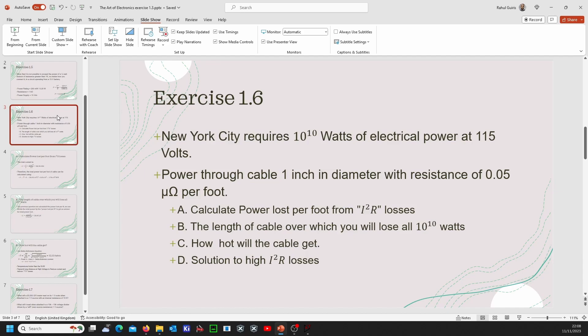The first part you need to calculate the power lost per foot from I squared R losses. The second part we need to calculate the length of cable where we will lose all of the power that is supplied by the system. The third part of the question we need to calculate how hot the cable will get with that power going through it. The last part of the question asks you to propose the solution.